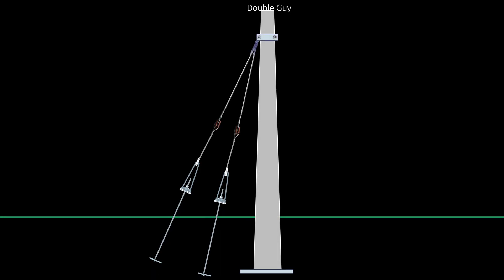Double Guy: A double guy of an electric pole refers to the installation of two separate guy wires attached to the same pole, which essentially provides extra stability and support by distributing the tension across two anchor points instead of just one. This type of staying or guying is often used on poles located in high wind areas and where the weight of the conductor is heavy.